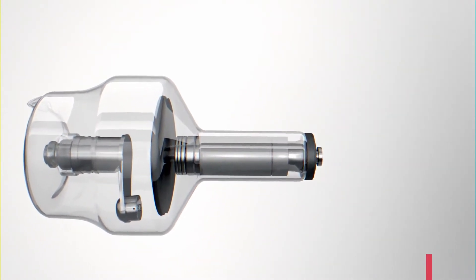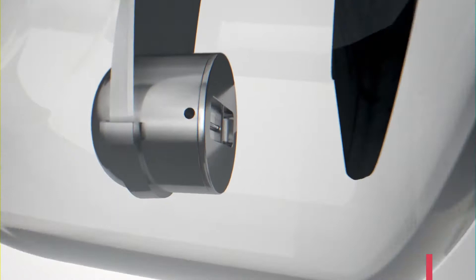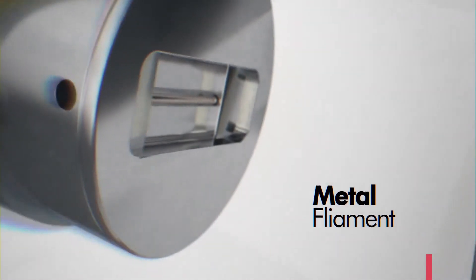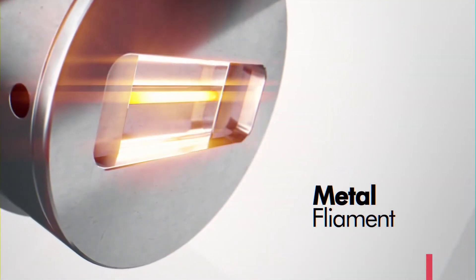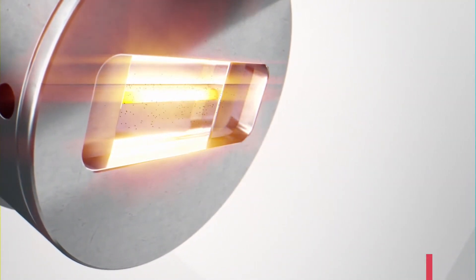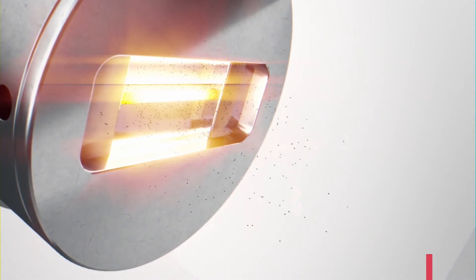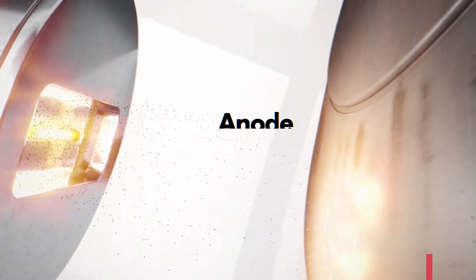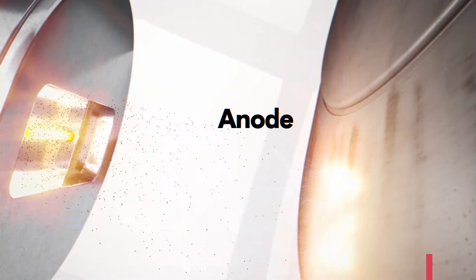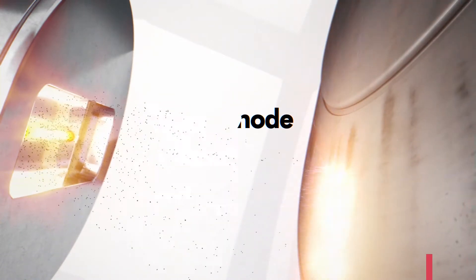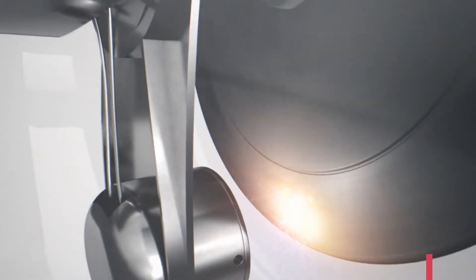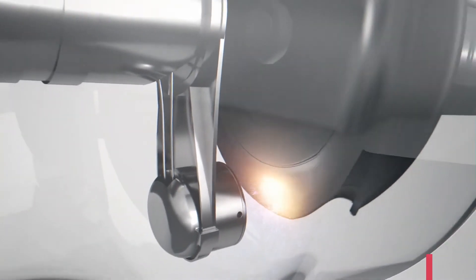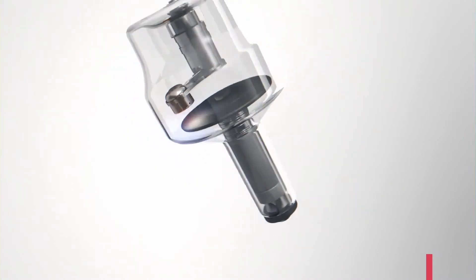It relies on heating a metal filament to 2,000 degrees Celsius. The heat then causes the filament to emit electrons that are accelerated toward an anode across from it, producing the x-rays upon collision. This process heats the anode to such a high degree that it must rotate to distribute the heat across its surface to prevent its meltdown.